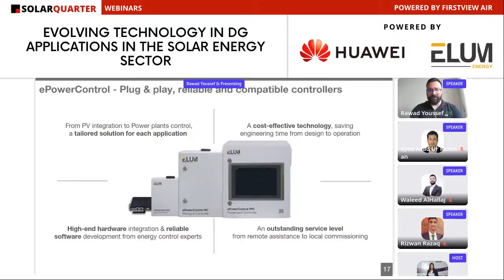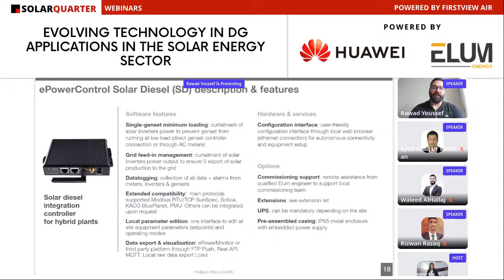We have the first family, which is the solar diesel, also known as hybrid fuel saver. With this controller, it's the first case, the pool grid. We installed these type of controllers to integrate the PV with the diesel genset and make sure that the genset is running at its minimum loading, to reduce fuel consumption and also reduce the maintenance problems that happen with the gensets.